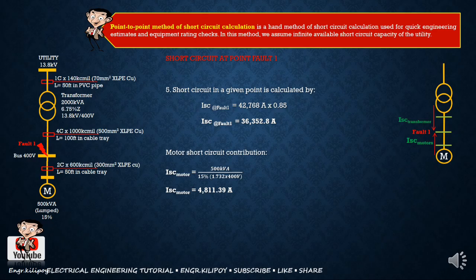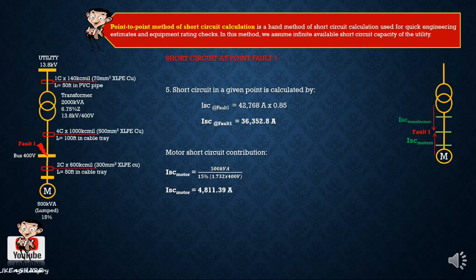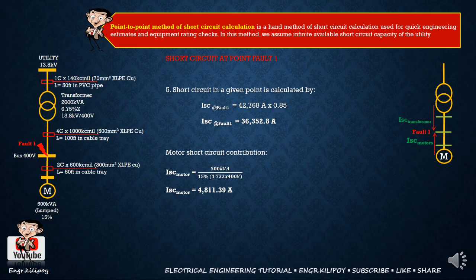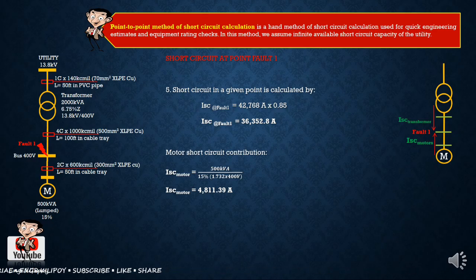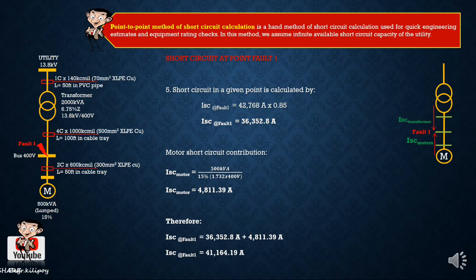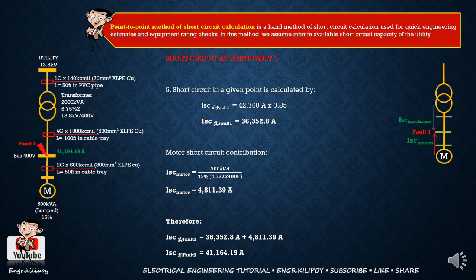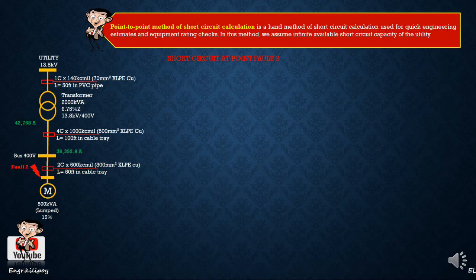Always remember, no, kapag nagkaroon ng 3-phase short circuit, lahat ng short circuit contributor pupunta lahat doon sa point ng short circuit. So in this case, karoon ka ng short circuit galing sa transformer mo, which is equivalent to 36,352.8 ampere plus yung motor load short circuit contribution na 4.8 kilo ampere. So magkakaroon tayo ng 41,164.19 ampere dito sa 400 volt bus. Ito yung value ng short circuit mo kapag nagkaroon ng 3-phase short circuit.